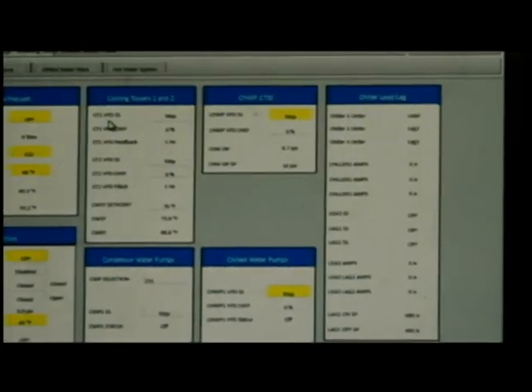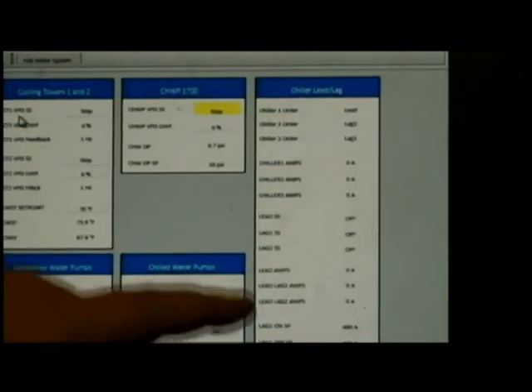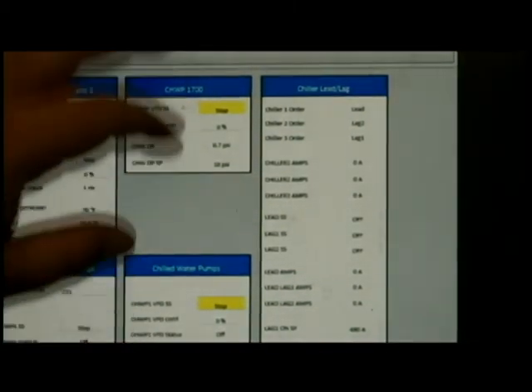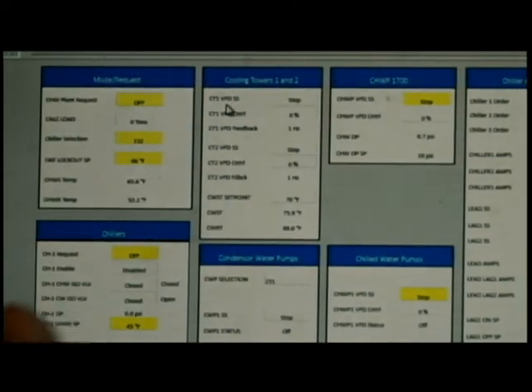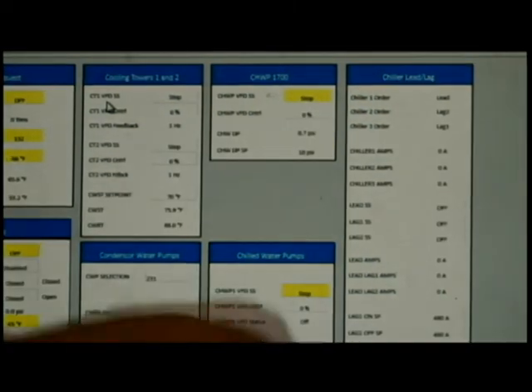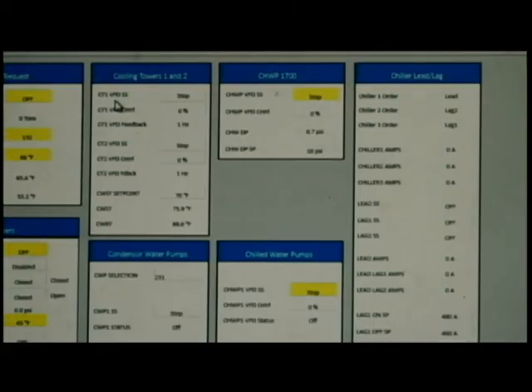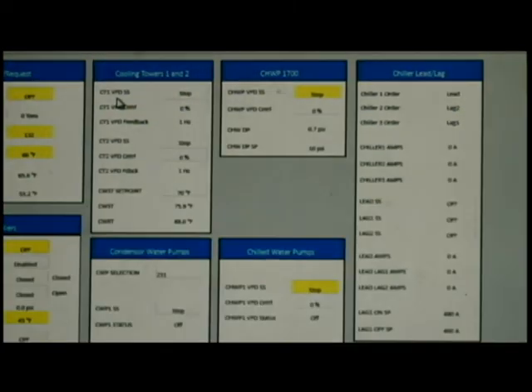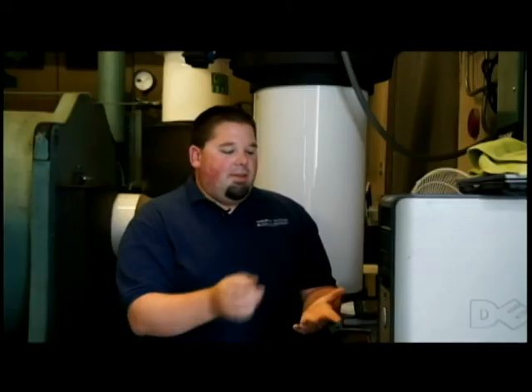And they're what enables the lag chiller to come on when needed. So over here on the far right of the chill water settings and set points graphic is the chiller lead lag information. We spell out the chiller order. In the mode request, we simply say 1-3-2 or 2-3-1. Over here, we actually call out that chiller one is lead, chiller two is lag two, and chiller three is lag one, meaning chiller one first, then number three, then number two, worst case scenario.